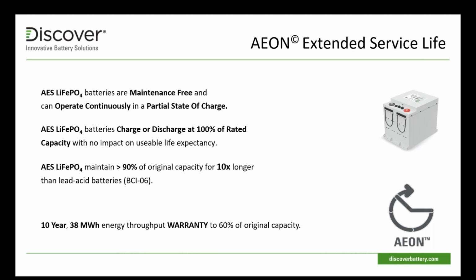Our warranty supports this, so we have a 10-year 38 megawatt hour throughput warranty to 60% of original capacity there. So even if you go through that 38 megawatt hours of energy throughput, you will have 60% of the capacity remaining or better to continue using the battery. That's not the end of its actual working life.